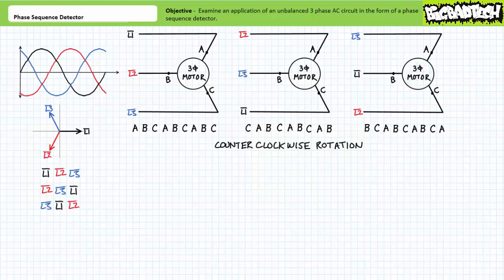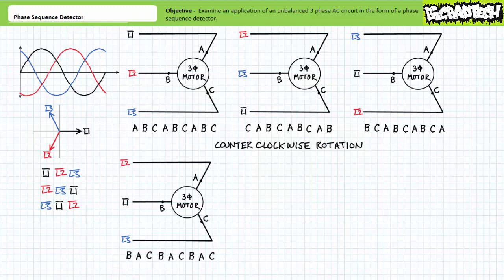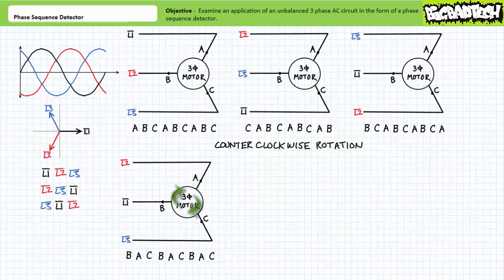Really, the only changing behavior for this system at the point of use occurs when any two phases swap seats on the bus. Consider L1 in seat B and L2 in seat A. As L1 voltage peaks it establishes a magnetic pole at terminal B, then as L2 voltage peaks at terminal A, then as L3 voltage peaks at terminal C. The process repeats itself, BAC, BAC, establishing clockwise rotation. This is opposite to our earlier observations and critical to applications such as reversing motor starters. Simply by swapping any two applied phases, the motor will rotate in the opposite direction.